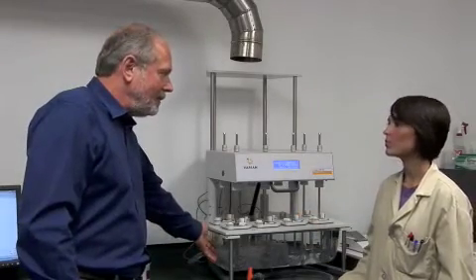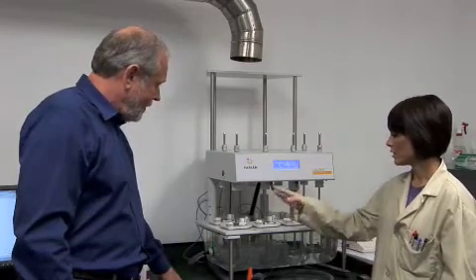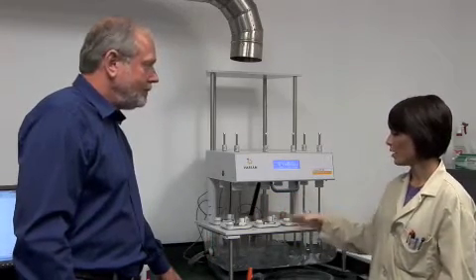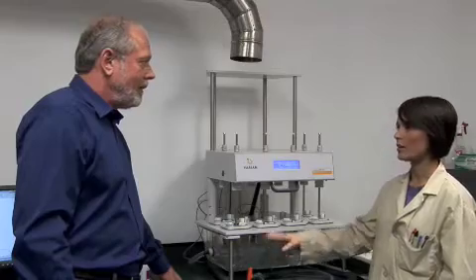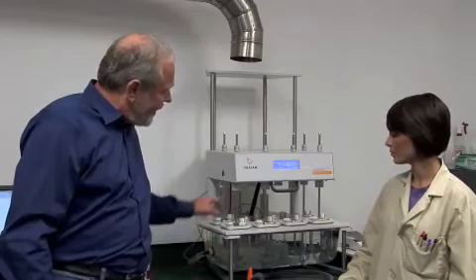So this is body temperature? Yes. These are set to body temperature, and each will simulate what the stomach does to make the nutrients bioavailable. In a normal test, the liquid inside each chamber is actually 0.1 N hydrochloric acid mixture, which is called for by the USP. That's to simulate a person with normal digestion.